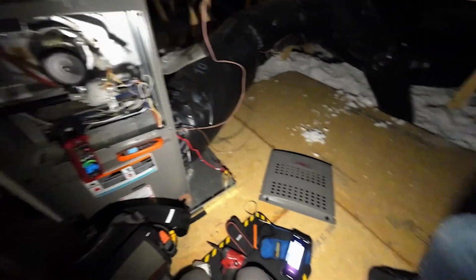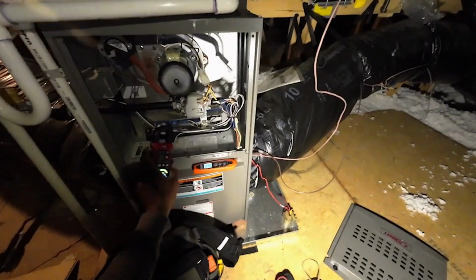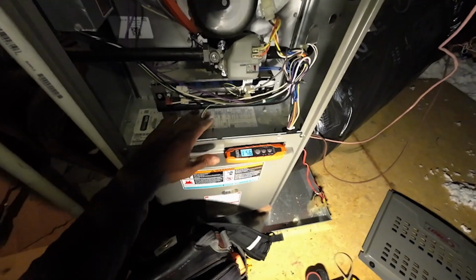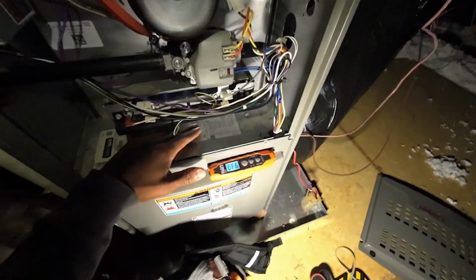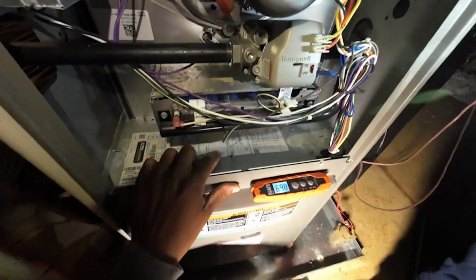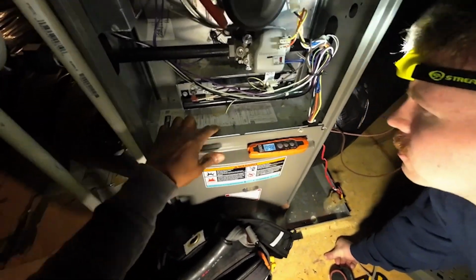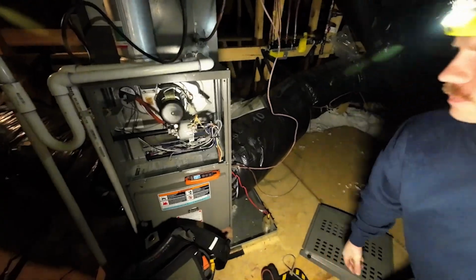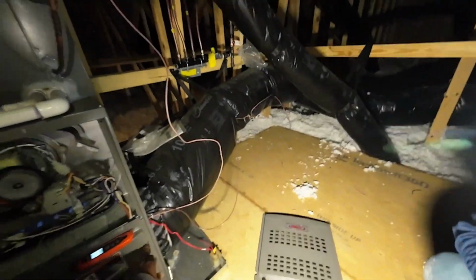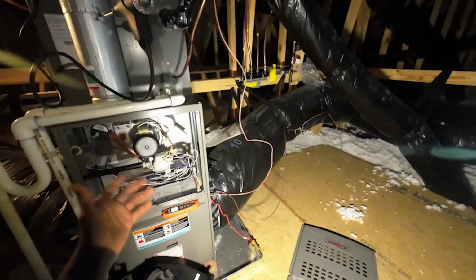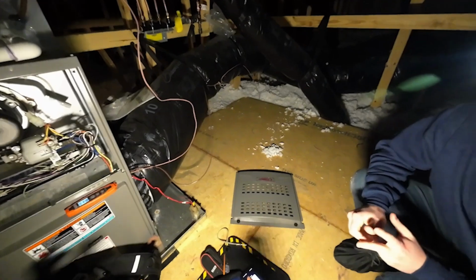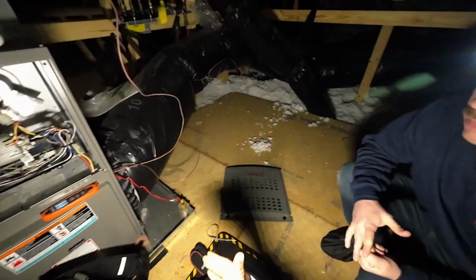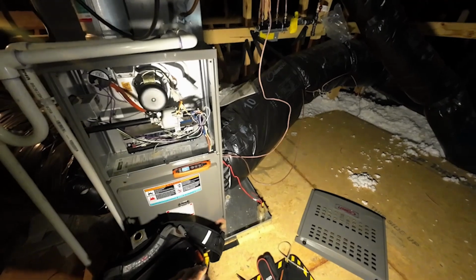So we got 119 degrees there, T1, T2. Pop this in here like such. That's going to get our temperature differential. Now you're going to see here on the nameplate, it's pretty important. Whenever you're doing maintenance, you want to study these nameplates, right? Temperature rise here, 40 to 70 degrees, and this piece of tape's on it, but I just know, so between 40 and 70. That means the difference in temperature of the air coming in here and the air leaving after the heat's been added to the air should be between 40 and 70. Now with an 80% furnace, you want that to be probably the middle to high, about 50 to 60. With a 90% you want it to be the medium to low range of the temp rise.